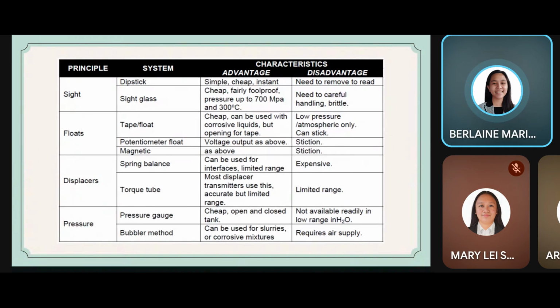Sa float methods naman po, the tape or float system is cheap and can be used with corrosive liquids, but it requires an opening for the tape. Its disadvantage is that it is only for low pressure or atmospheric conditions and it can stick din po. The potentiometer float gives a voltage output as the float moves with the liquid. Its disadvantage is stiction, which means static friction causing the float to stick and not move freely. The magnetic float works similarly, but it uses magnetic force to indicate the level. Its disadvantage is also stiction.